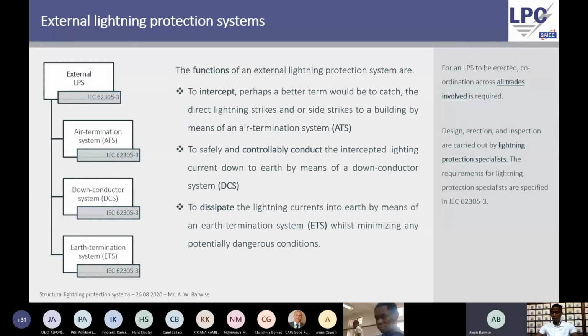And then once we've intercepted that lightning strike, we have to find a way to safely and controllably, two very important words, conduct this intercepted lightning down to the earthing system or to the earth itself. And this is done via the down conductor system. Finally, once the currents have been intercepted and controlled all the way down to earth, we need to find a means to dissipate these currents into what is better known as an earth electrode or an earthing system. The terminology used in the standard refers to an earth termination system. And we have to do this whilst minimizing potentially dangerous conditions. So we see the words safe and controlled, and the words potentially dangerous conditions. We remember again that a lightning protection system is there to protect the building as well as the occupants, to create safe and effective ways of dealing with the strike.